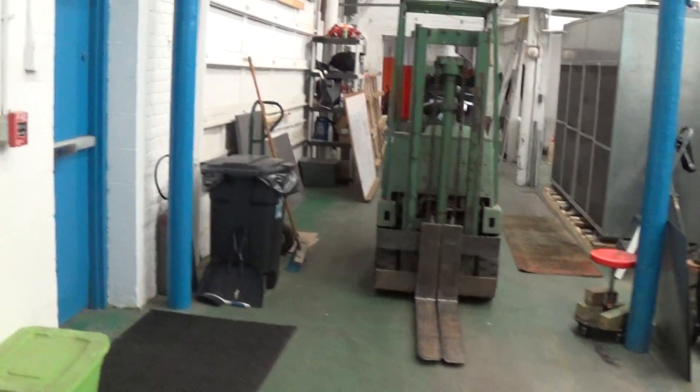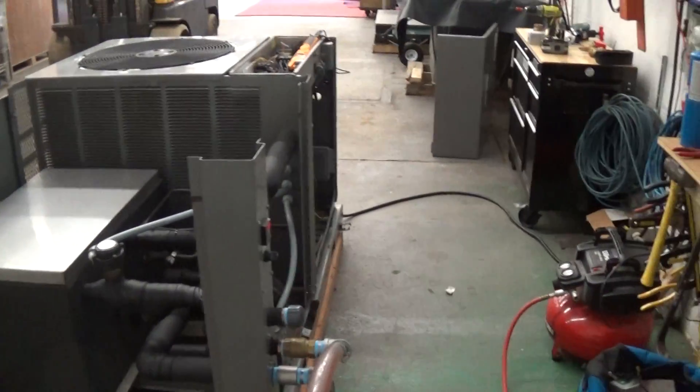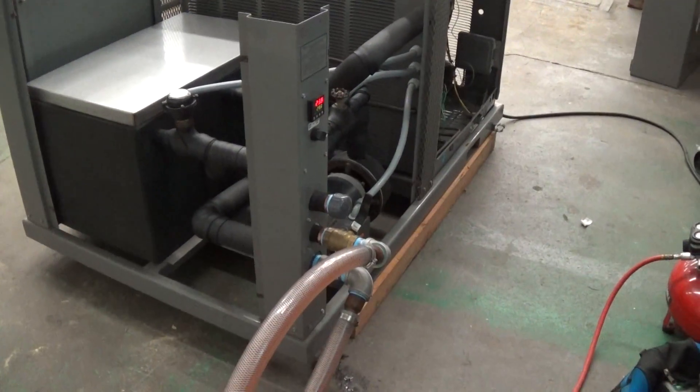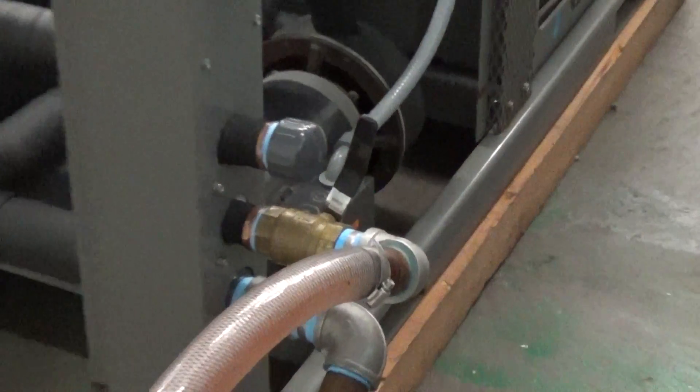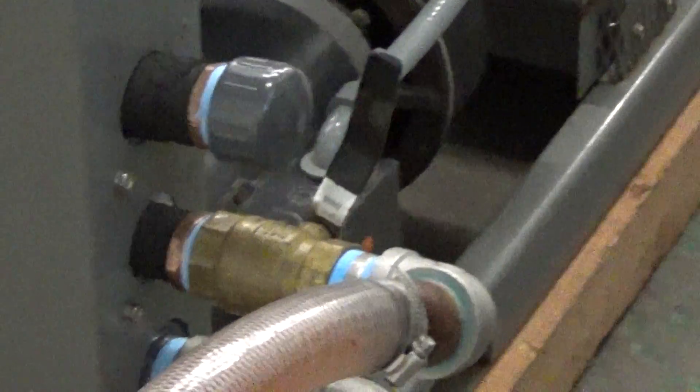Fixed it and repainted that top cover. When all the covers are on it is a little bit quieter. Part of the reason this pump has a little bit of noise to it is because just with our loop here, we have to have it almost 95% shut off.